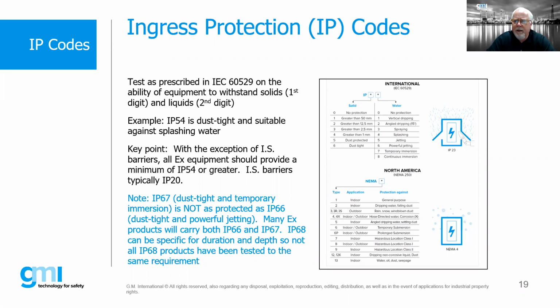There is one little thing within IP codes that's important to note. IP66 is a more onerous test, the powerful jetting test, than actually IP67. So let's not make the assumption that a product that is IP67 is suitable for an IP66 application. So what manufacturers have actually done is, with regards to products that meet both of those applications, they will dual market with both IP66/67, because there is a little bit of confusion.